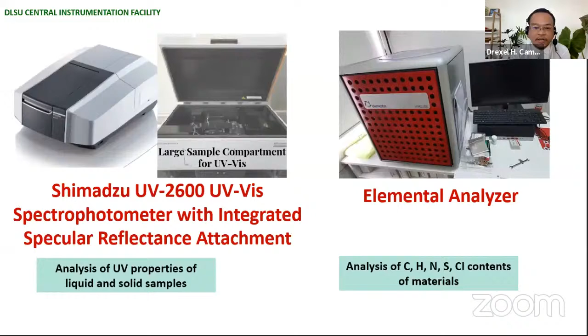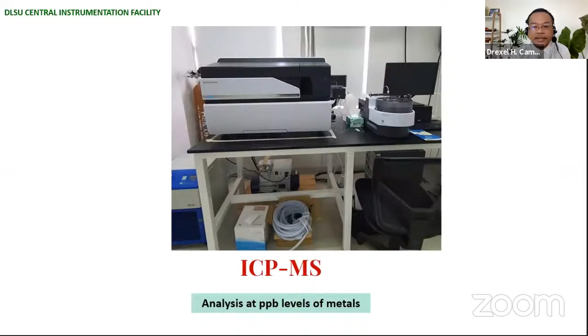We also have an elemental analyzer. This is a very important instrument to determine and confirm really the structure of our compound by determining the percentage of carbon, hydrogen, nitrogen, sulfur, chlorine. And if you're reporting a novel compound, this elemental analysis is essential information that you should report. And we do have ICP-MS, which is used to analyze metals at the ppb level.